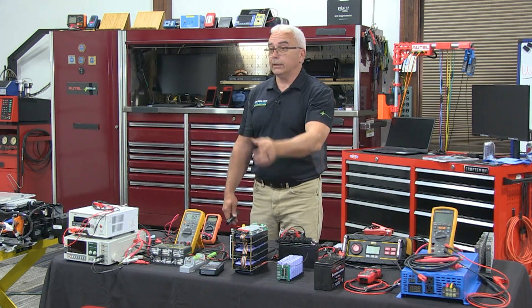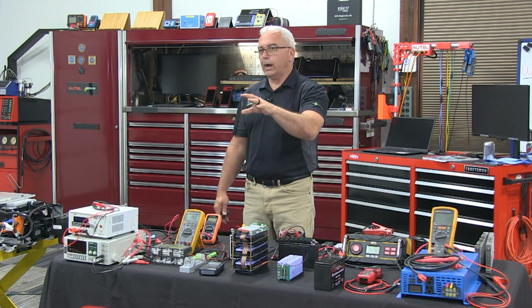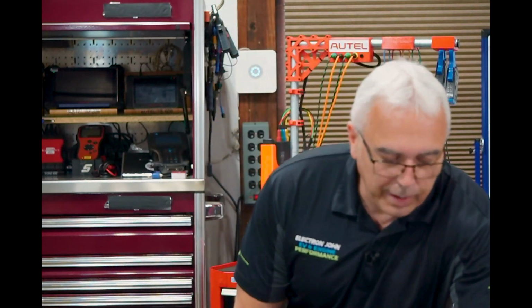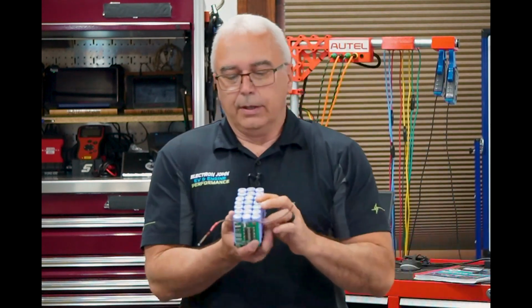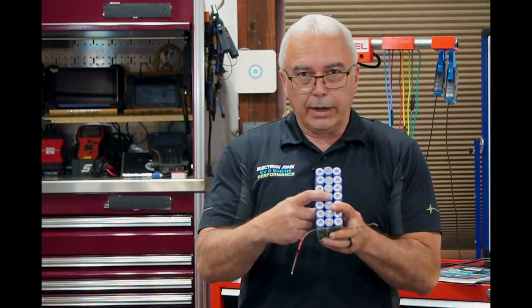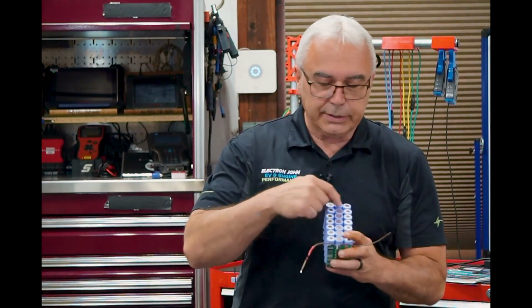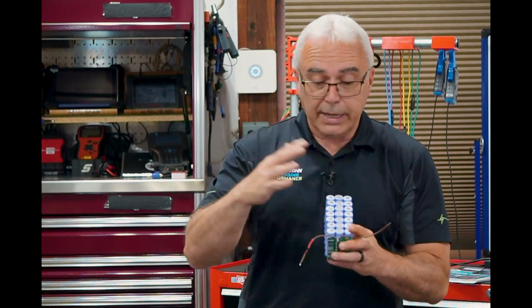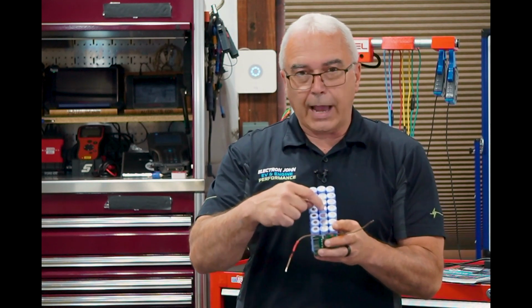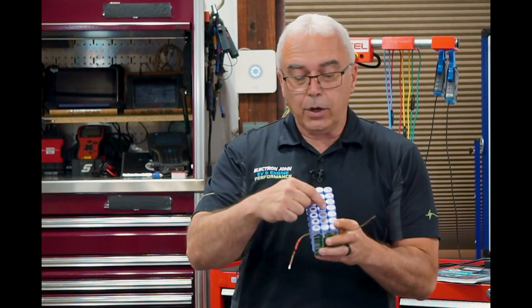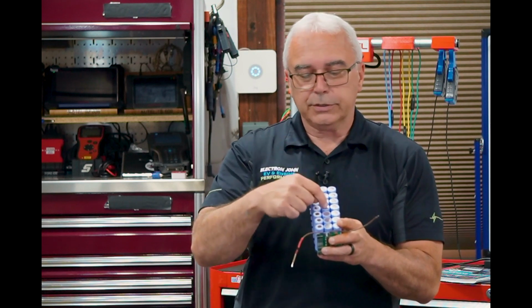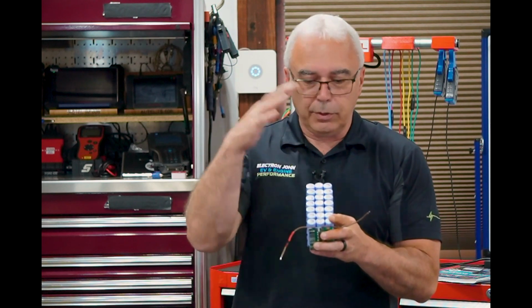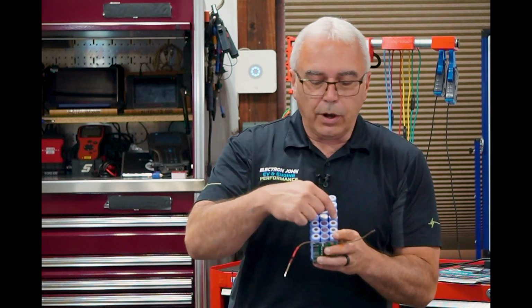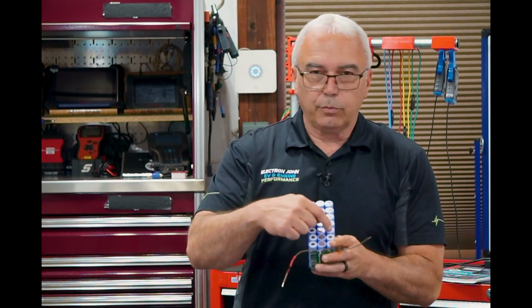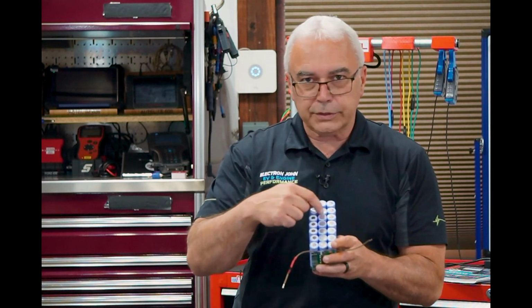They spray water on it. That's important too. You'll see the why here in a second. They spray water on it, they put the fire out. But remember, from this makeup, this guy in the middle caught on fire. He increased the temperature of all these other ones. So technically, even though we had the oxygen from the cathode all present here, we put the fire out, but we already started the thermal runaway of all these other cells.